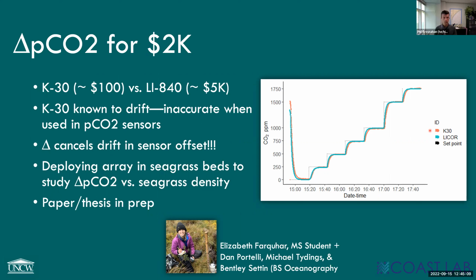But what's really nice, this third bullet point here, the delta measurement, by subtracting the air side from the water side, we're canceling any drift or any inaccuracy that might occur in terms of the offset. And so we're not too worried about the overall accuracy, as long as there isn't a significant slope to that inaccuracy, as long as it's not a large percentage, or as long as we're able to characterize it well, we believe that we can get a really robust delta. And we've already seen this in our initial field deployments. We are excited to start deploying it in some seagrass beds and looking at delta PCO2 versus seagrass density.